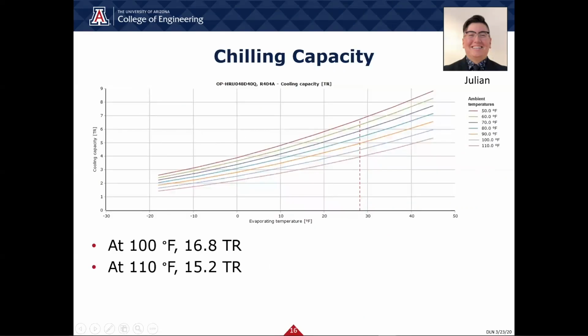The projected chilling capacity was found using the Danfoss software provided to the team by the chiller manufacturer. After selecting various operating parameters for the chiller condensing units, we were able to get these plots showing the chilling capacity and power consumption at the glycol exiting temperature of 28 degrees Fahrenheit. It is important to note that these plots show the capacity and power consumption for one condensing unit. The two chillers at Barrio both have two condensing units, therefore the values are multiplied by 4.